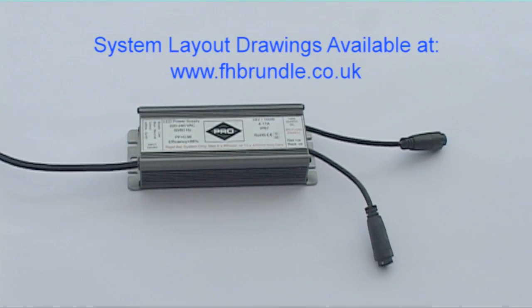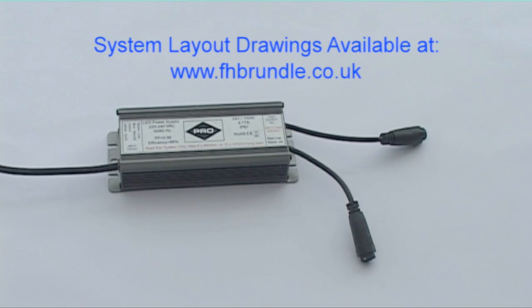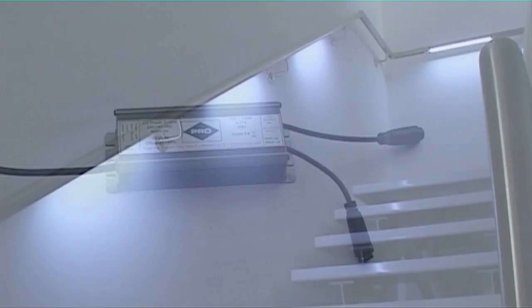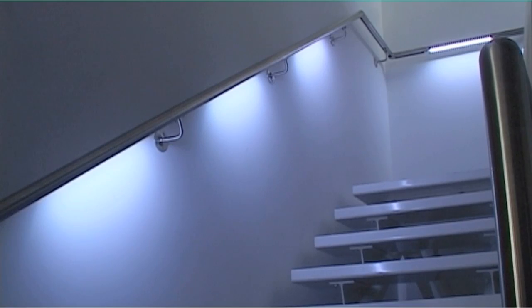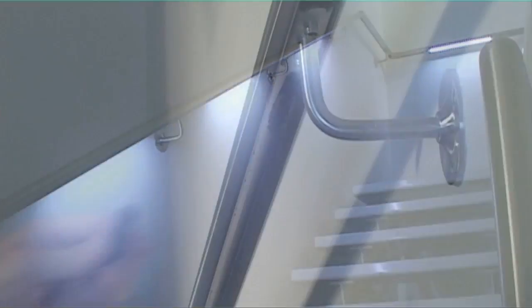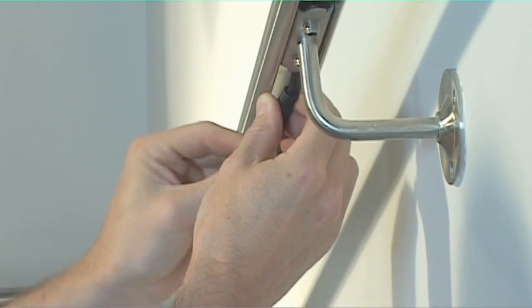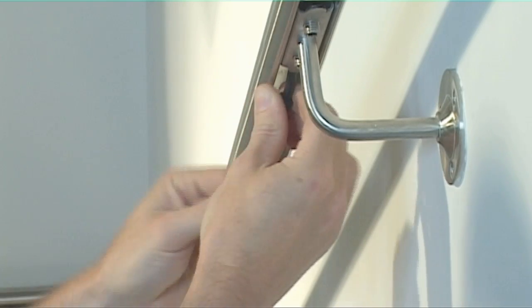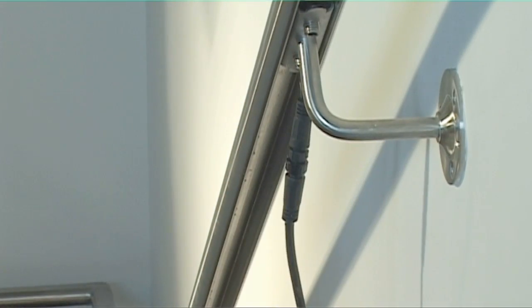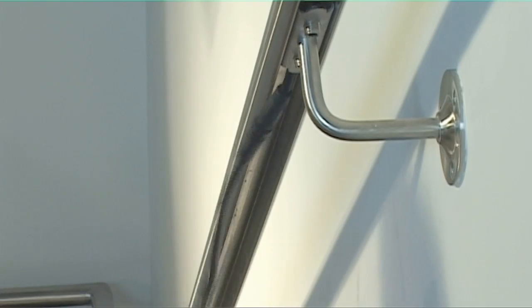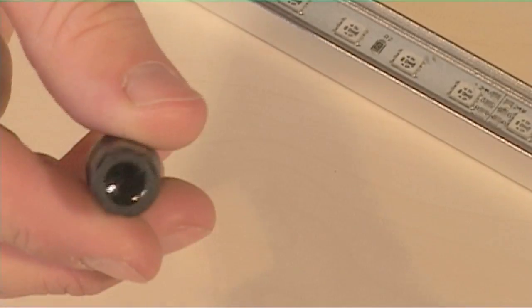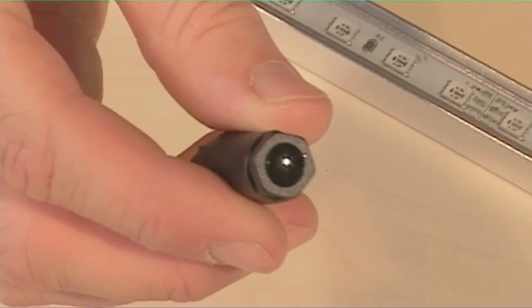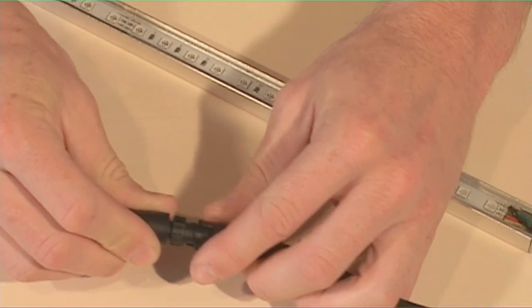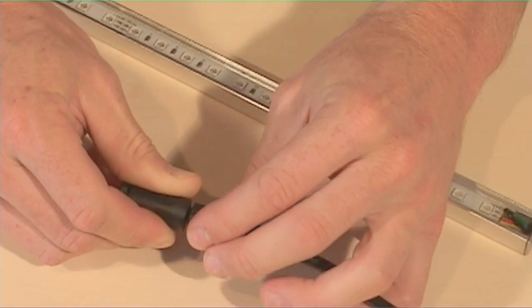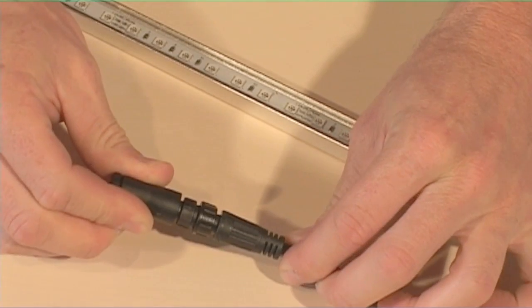It's best practice to have the transformer in the middle of a run of lights and to use both outputs from the transformer, which between them will power up to 6 long or 12 short LED bars. The bars are daisy-chained like so. Terminate the end of a run of rigid bars with a 2-pin end cap. Line up the two arrows, click into place.